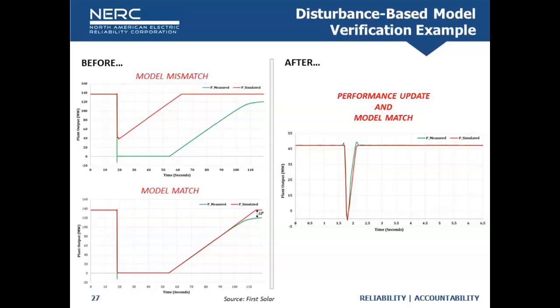But the real success story is on the right side, where they made a performance update followed by a model update. They realized a 35-second momentary cessation was no good and changed their operating mode. You can see the plant output drop when the fault occurs, as expected, whether in reactive current injection or a short-duration momentary cessation—but that response looks a lot better. The unit went into some active power reduction and recovered to pre-disturbance value within about 250 to 300 milliseconds, which is fantastic. The model does a pretty good job of matching reality there too—so it's kind of a double success story.